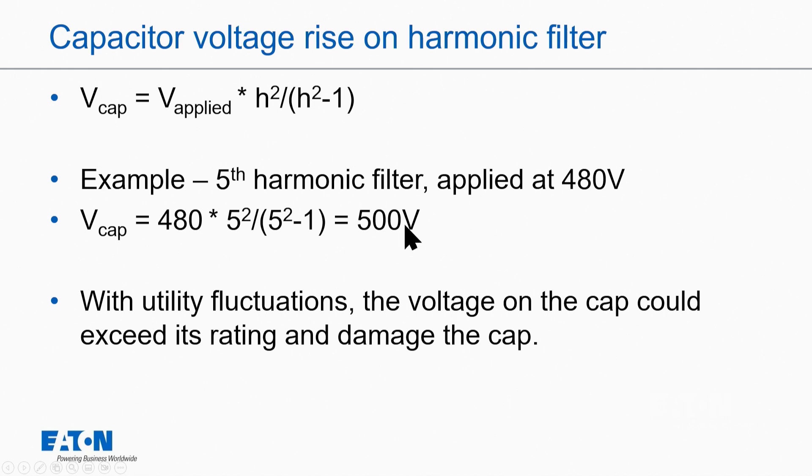Now, that's probably OK and within the limits of the capacitor. They usually can take about 110 percent voltage by the capacitor standards. But the problem is that's if I'm running at 480 volts. If I'm running at a higher voltage, which is very common today with utility systems, then that means this voltage starts to approach a much higher level, which then can stress the capacitor and cause it to fail.